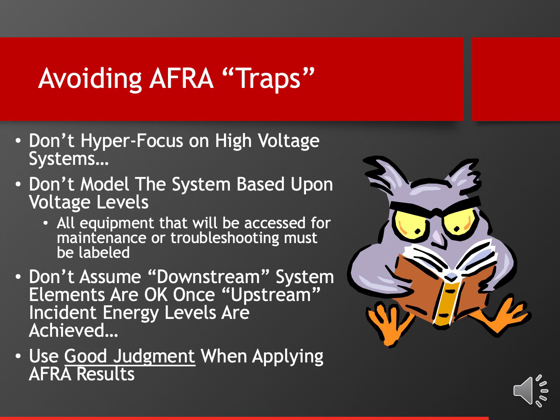Don't model a system based on voltage levels. Some companies will just stop at 480 volts and they won't go any lower than that into the system. Once again, pay attention to the calculated incident energy. We've had 208 volt systems that have very, very high incident energy levels, and we've had arc flash events on 208 systems where it blew the transformer right off the wall. And so don't assume that your 208 system is always a safer system than 480 or above, because that may not be the case.